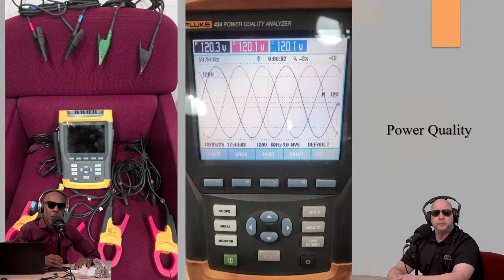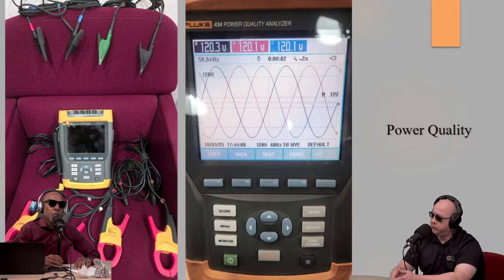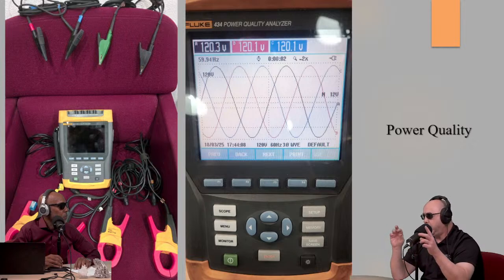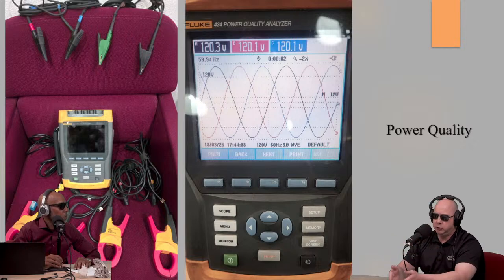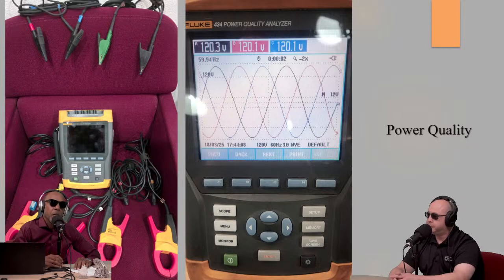How much load is typically put on a unit when being tested? It varies on what your setup is. If I've got a 20K frame with only 2 power modules, it depends on the load bank settings and the combination of those. But usually I'll run it at about 50 to 60% load to simulate what's in the field. They can go higher, but I usually do 50 to 60%, typically for 3 to 4 hours.